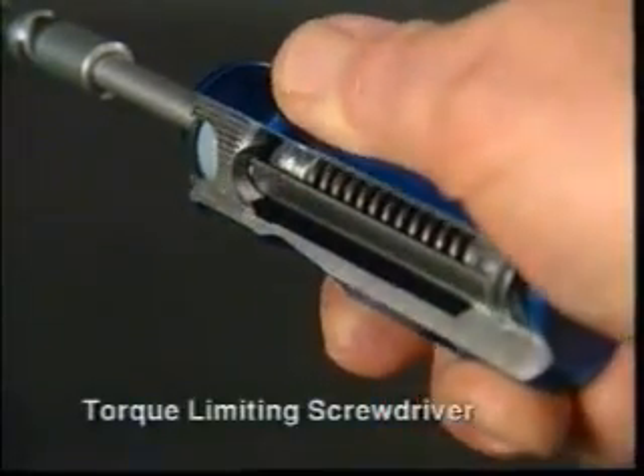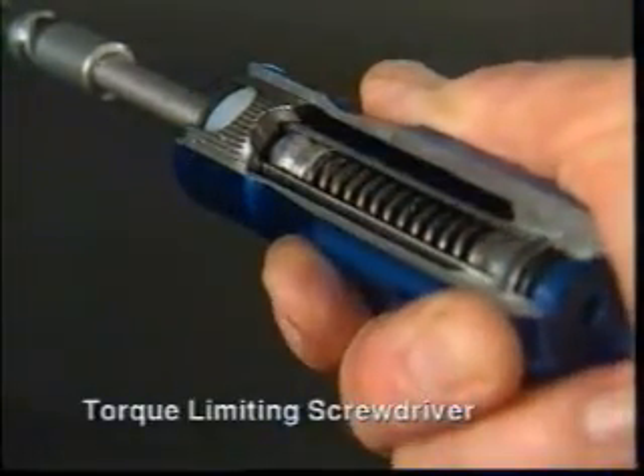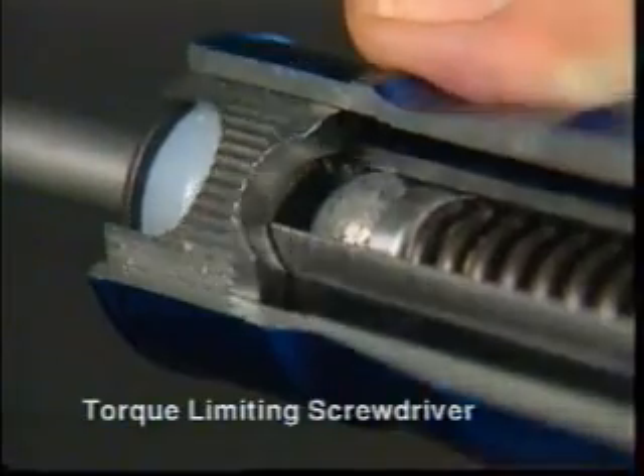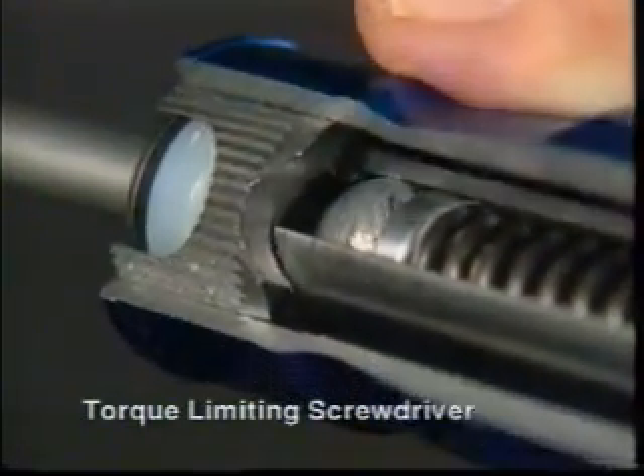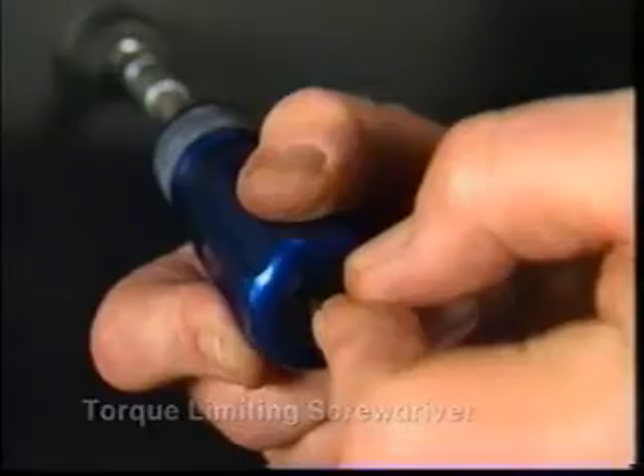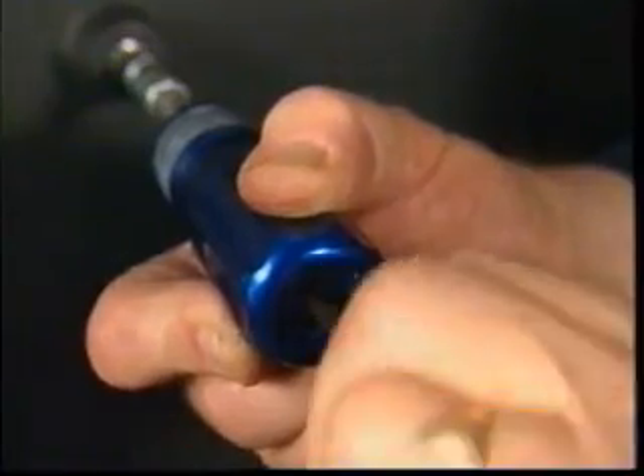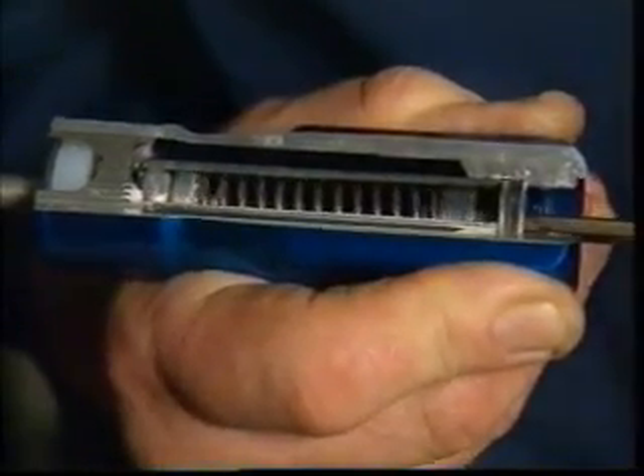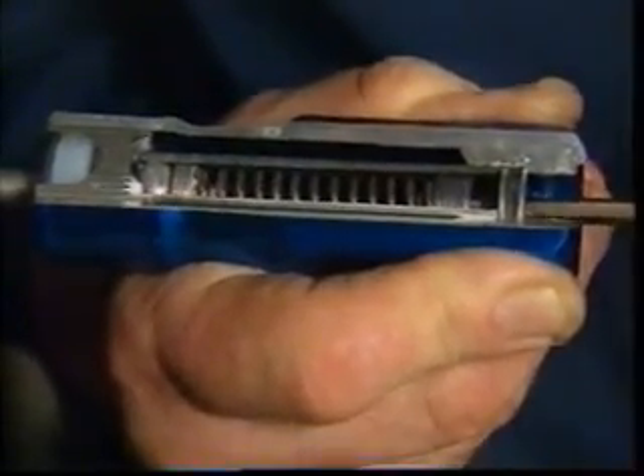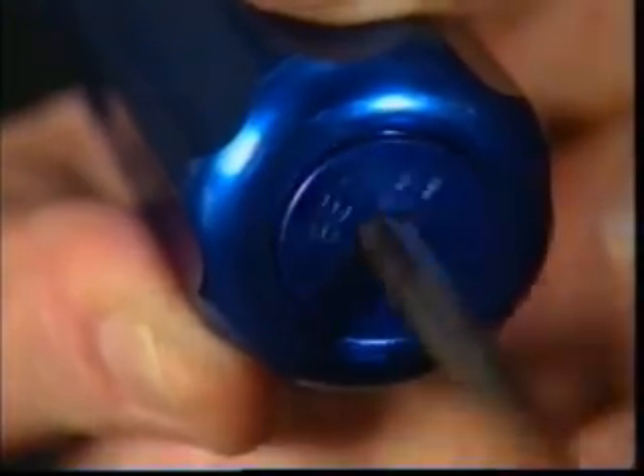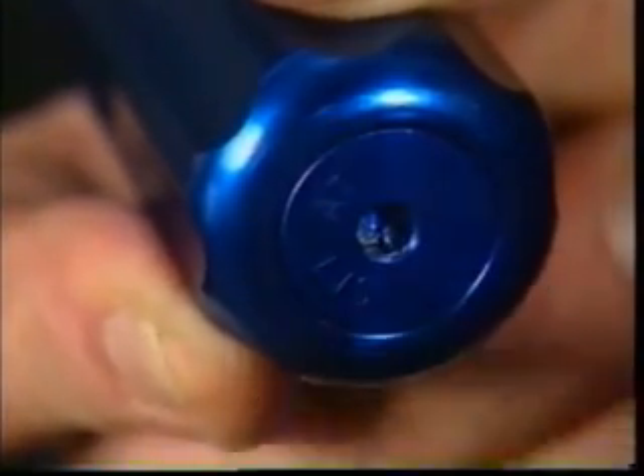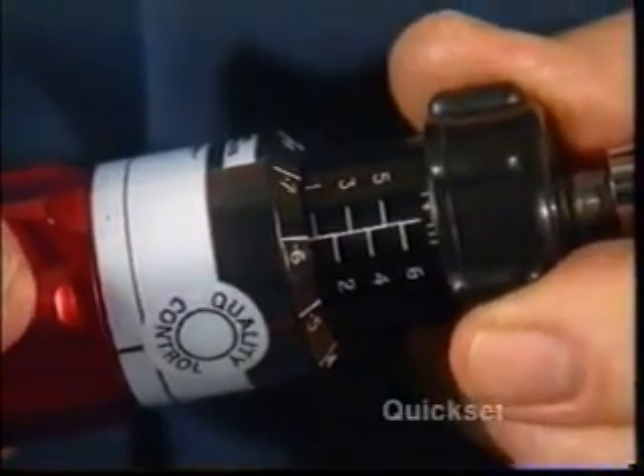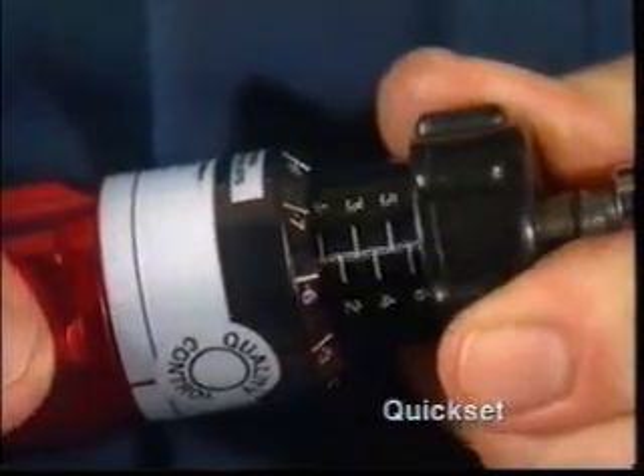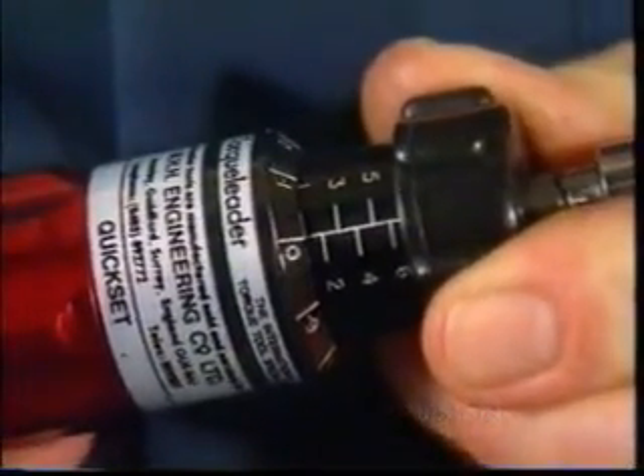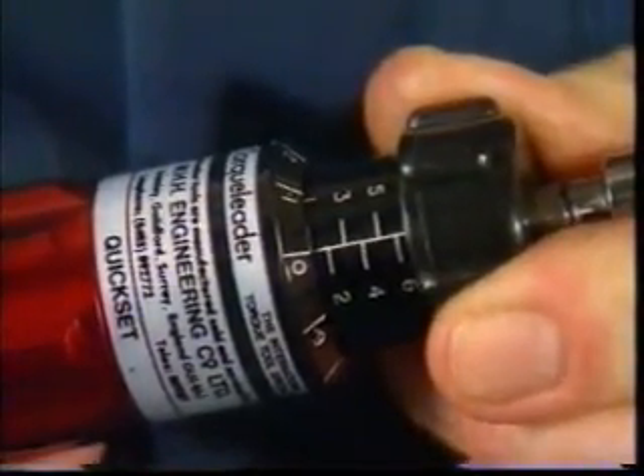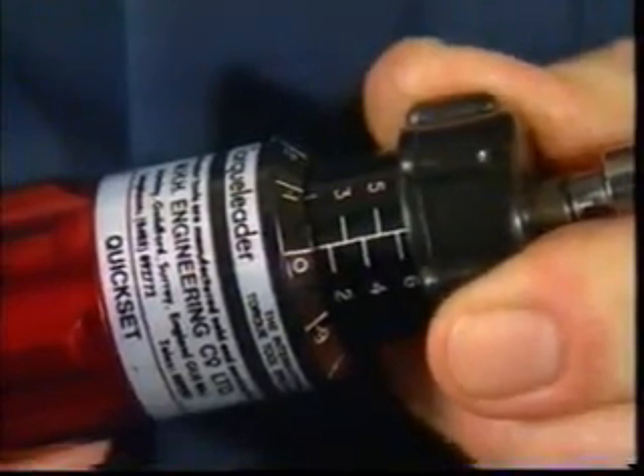For the application of lower torque values, a similar system to the TSN mechanism, using a large ball and 3 smaller ones pressed against a radial cam in the handle, is used in torqueleaders' torque-limiting screwdrivers. The torque setting is adjusted by altering the compression of the spring. Again, the setting mechanism is protected by a dust cap to prevent unauthorized adjustment. With the quickset version of the torque-limiting screwdriver, however, the operator is able to set the required torque value by adjusting the micrometer-calibrated scale.